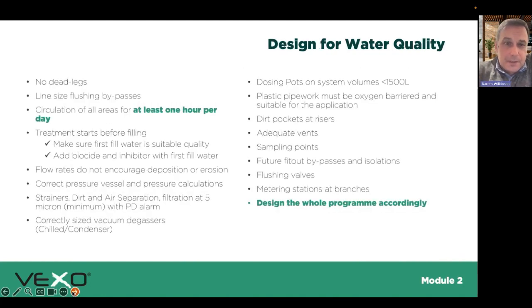So we want to design for water quality, avoid any dead legs, make sure we've got line size flushing bypasses. I've seen systems with 6-inch district network pipework and a 2-inch bypass, and there's absolutely no way the contractor's ever going to move anything sitting in that pipework through a 2-inch bypass. You have to have line size bypasses realistically, particularly if somebody's got to bring in temporary pumps. Treatment starts before filling. So again, make sure you know what the water quality is. Typically add a biocide and inhibitor with your first fill. There are much lower hazard risk additives that can be added at that stage.